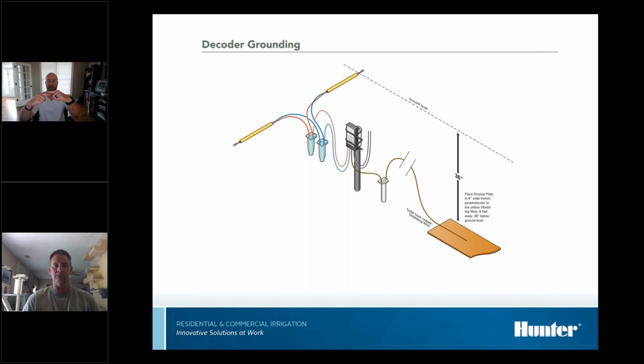The acorn connectors allow the 2 ground wires to sit like this, because what are we doing? We're cutting down on resistance. If you splice it and twist it, that creates resistance, and we want the least amount possible. So we use 2 little acorn clamps, clamp the ground wire like this, move it out at a right angle to the wire path, at least 8 feet away, and then place the ground plate there.